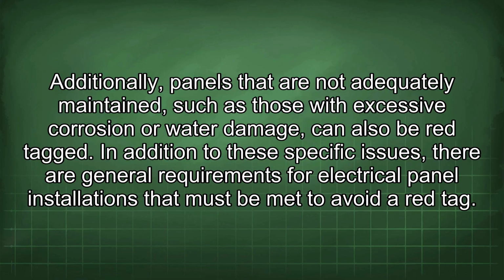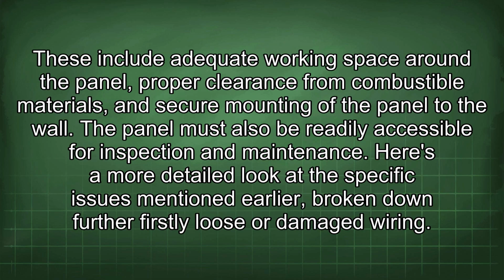In addition to these specific issues, there are general requirements for electrical panel installations that must be met to avoid a red tag. These include adequate working space around the panel, proper clearance from combustible materials, and secure mounting of the panel to the wall. The panel must also be readily accessible for inspection and maintenance. Here's a more detailed look at the specific issues mentioned earlier, broken down further.